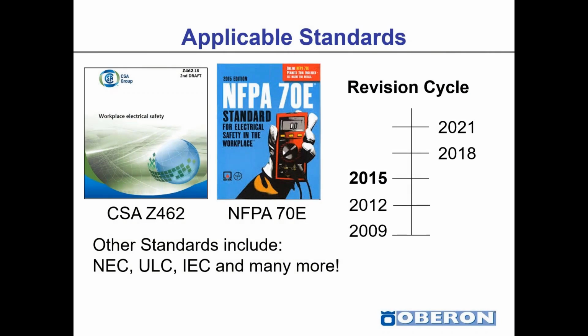The applicable standards in the industry that apply to Arc Flash PPE, I'm located in Canada, so I put CSA Z462, and there's also the NFPA 70E, which is the global seed document or seed standard for any workplace electrical safety. Other standards include NEC, ULC, IEC, and many more. We have a revision cycle here in North America for the NFPA 70E and CSA Z462. At the time of this presentation, the most current edition or publication is 2015. We are about to introduce and publish the 2018 edition. And as part of the technical committee, we are working on 2021 and future editions of the standard.